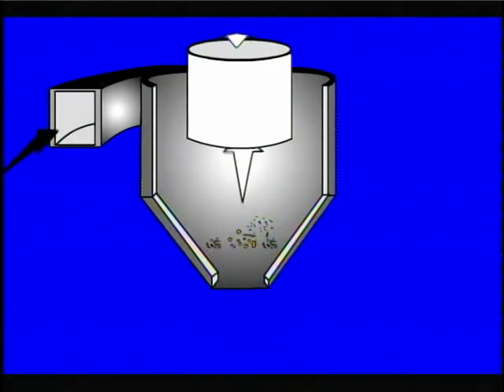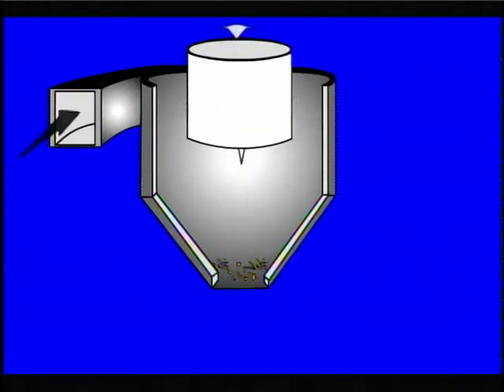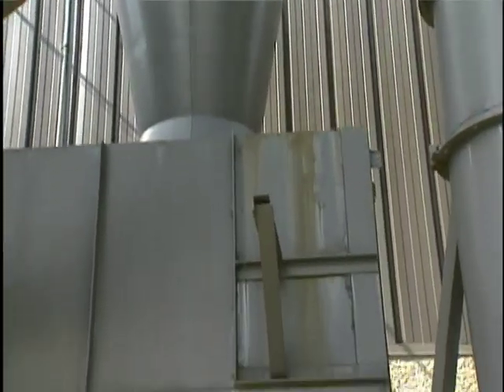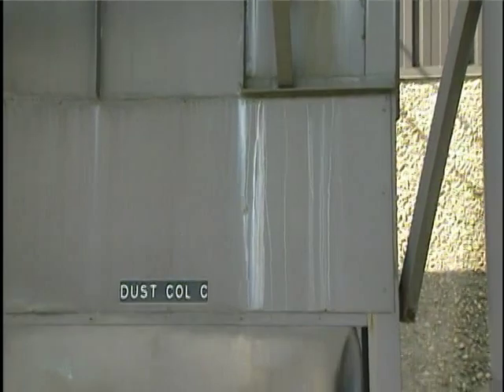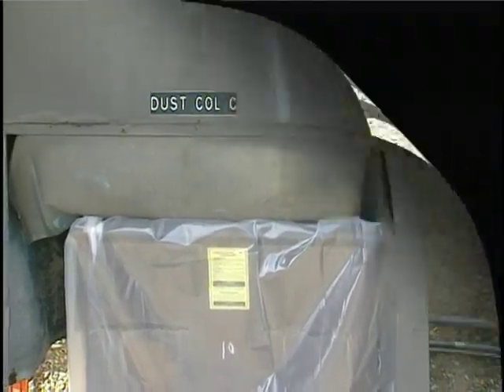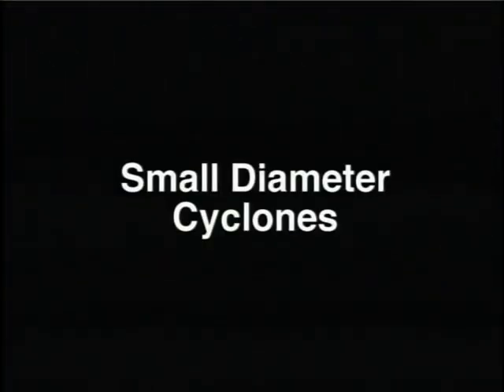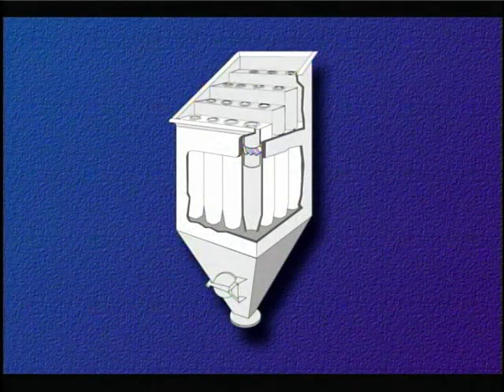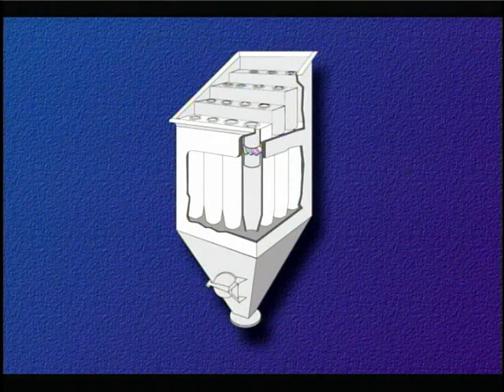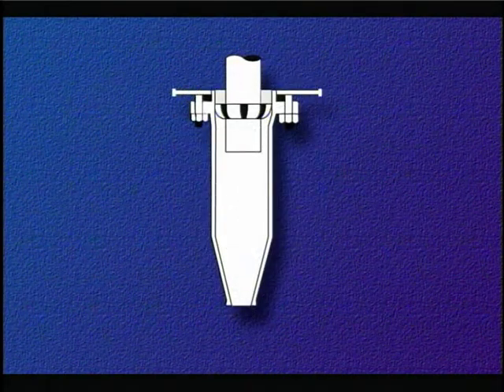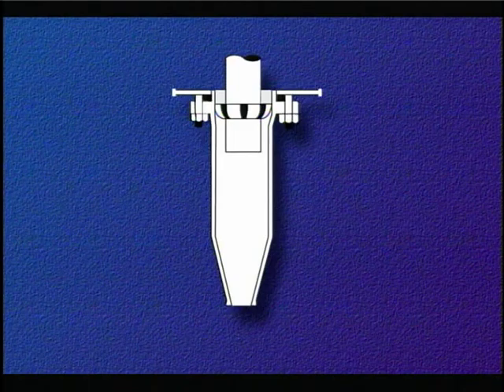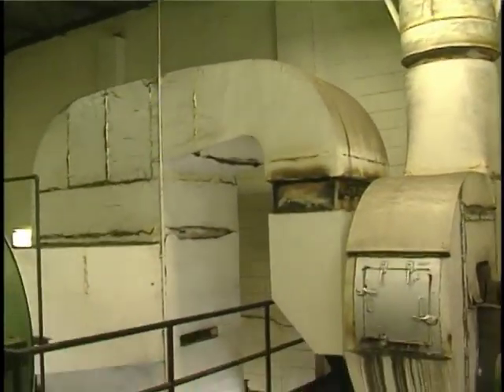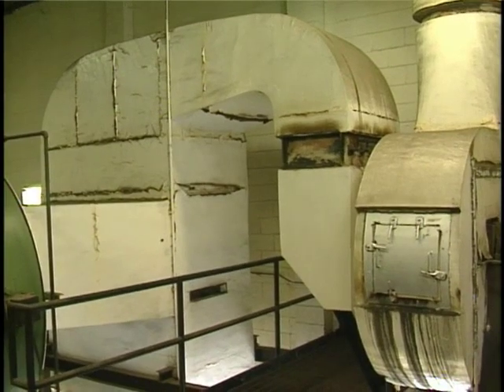Additional separation occurs as the gas stream reverses direction near the bottom of the cone and moves upward and out of the exit tube. Particles exiting the cone section are usually collected in a hopper before being removed for disposal. Small diameter cyclones are typically 6 to 12 inches in diameter and, like large diameter cyclones, consist of a constant diameter upper section and a tapering lower section.